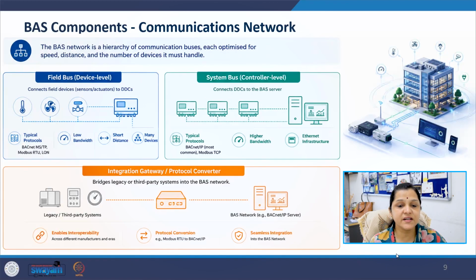Next is the integration gateway. Integration gateways are also important. These devices connect legacy systems or third-party equipment with the building automation network. For example, Modbus RTU chillers may communicate with a BACnet IP server through a protocol converter. Communication networks therefore provide the interoperability required for integrated building operations.